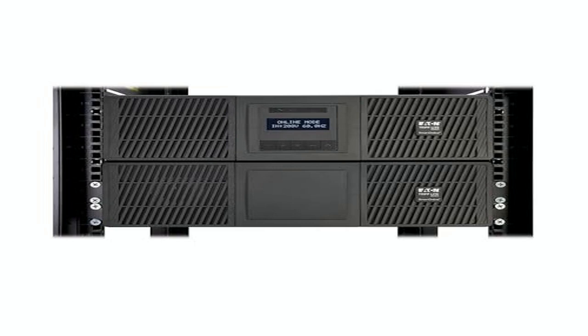Let's talk about practical strengths. The extended runtime option is one of those nice-to-have features that becomes must-have when a power outage hits during a critical backup window. With the optional extended battery packs, you can push runtime from the standard 10-minute window at full load to over half an hour, giving you enough time to gracefully shut down servers or switch to a secondary power source. In a scenario where a small business is processing end-of-day transactions, that extra cushion can prevent data loss and keep the accounting software from crashing.